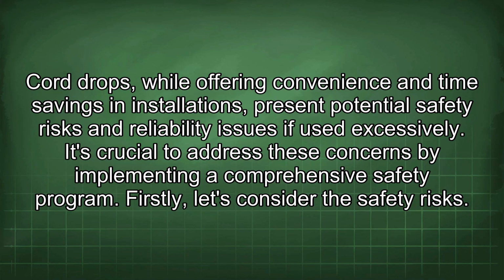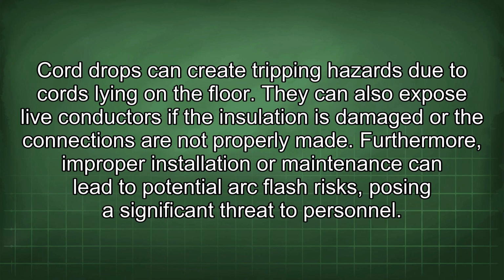Cord drops, while offering convenience and time savings in installations, present potential safety risks and reliability issues if used excessively. It's crucial to address these concerns by implementing a comprehensive safety program. Firstly, let's consider the safety risks. Cord drops can create tripping hazards due to cords lying on the floor. They can also expose live conductors if the insulation is damaged or the connections are not properly made. Furthermore, improper installation or maintenance can lead to potential arc flash risks, posing a significant threat to personnel.